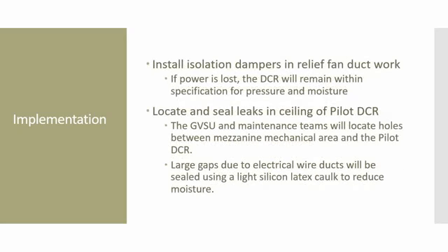Isolation dampers will be installed in the relief fan ductwork. This will reactively prevent the pressure and moisture from changing within the dry clean room. The GVSU and Clarios maintenance team will locate and seal leaks within the ceiling of the pilot DCR. The large gaps from electrical wire ducts will be sealed with a silicone latex caulk, which will reduce the amount of moisture that enters the room.